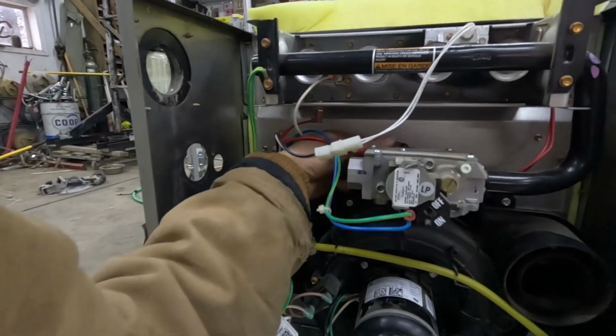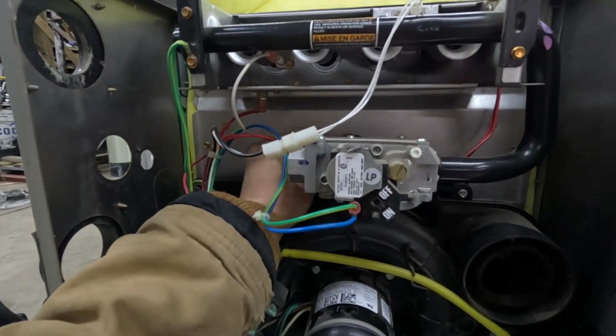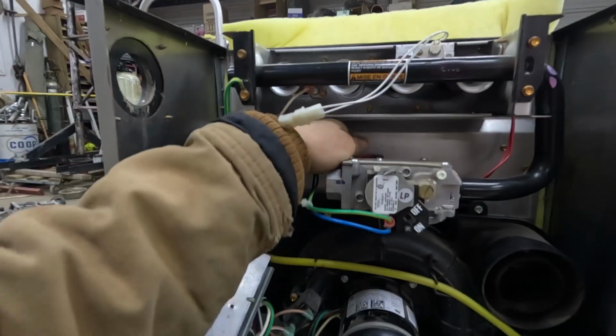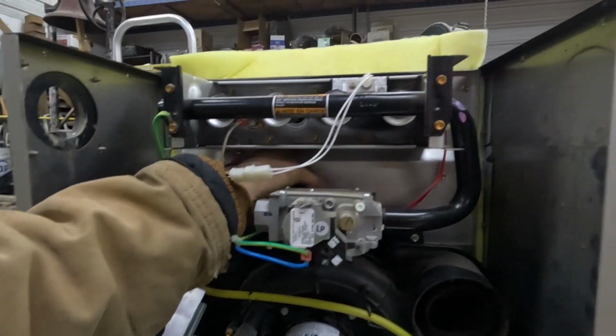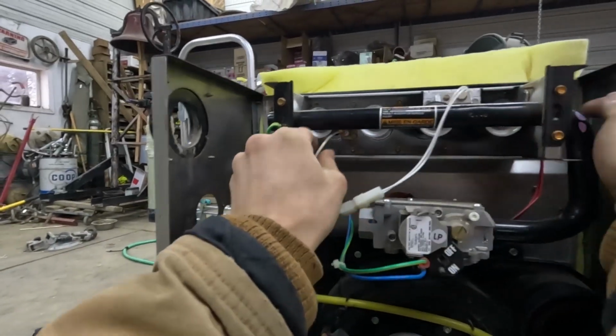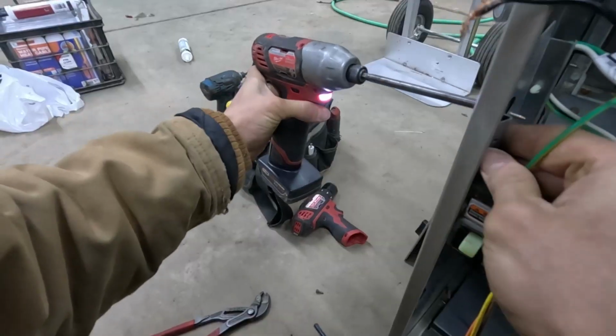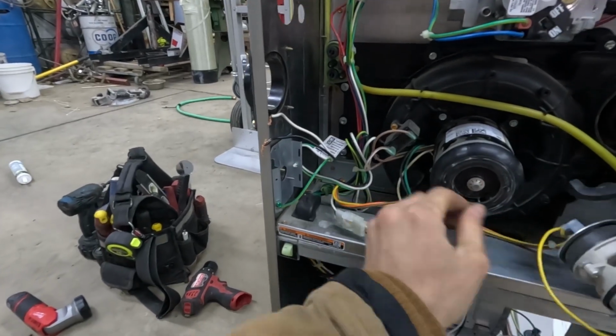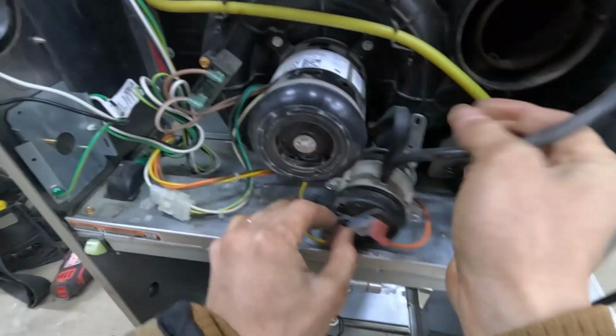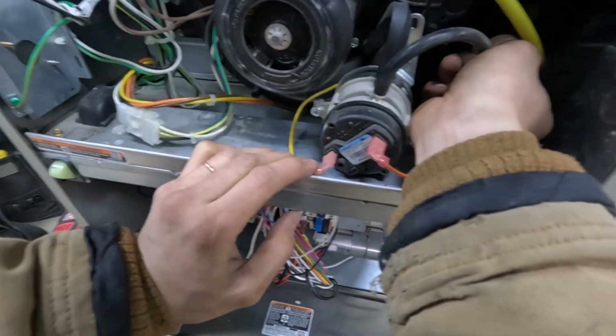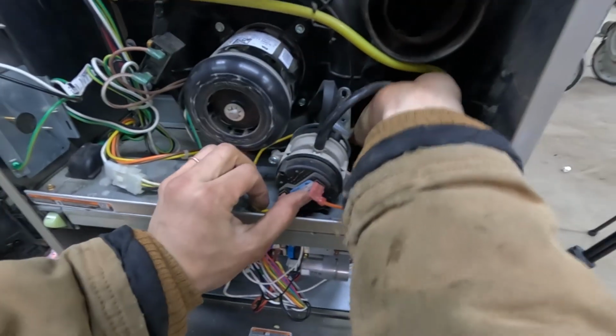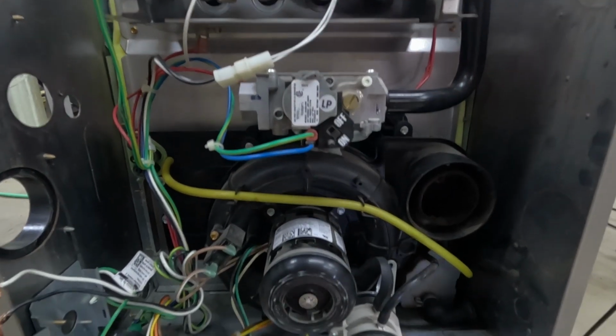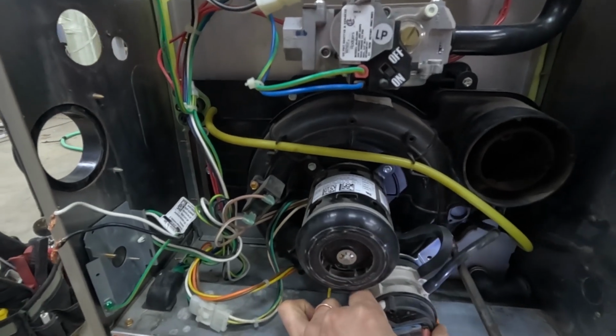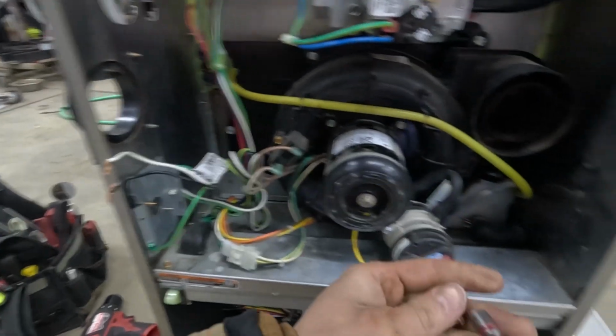Now we can plug stuff back in. We just have this limit switch back here that we unplugged—that's all still plugged in. Lastly, our pressure switch: this back one hooks onto the combustion blower right there, and this one goes over to this nipple on the collector box, very hard to see. These ones are threading into plastic, so we have to be really careful not to over torque them.